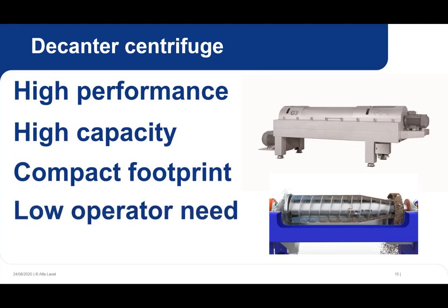It is a high-speed piece of rotating equipment, though, so requires periodic maintenance to address wear and tear. It also has higher power consumption than other types of dewatering equipment, such as a belt press. It is fully enclosed, which is helpful in reducing odor. You often see decanter centrifuges selected for medium to large wastewater treatment plants because the footprint required for other technologies would be much, much larger.